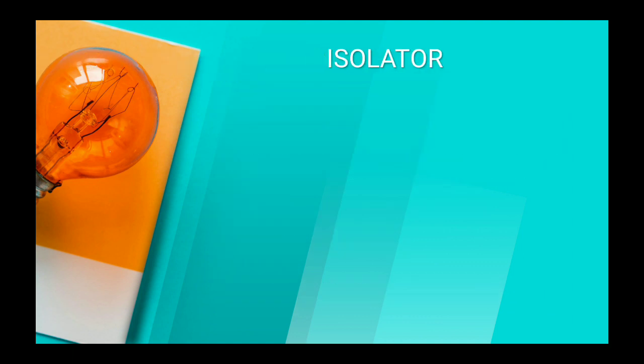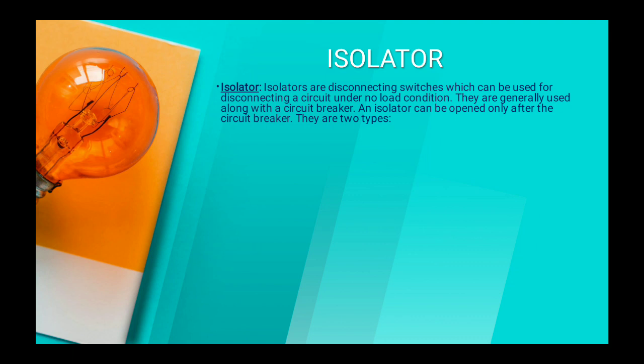Now the next circuit interruption device is the isolator. Isolator means the isolation switch which isolates the healthy electrical part or healthy electrical line from the faulty line. Isolators are disconnecting switches which can be used to disconnect a circuit under no load condition. You can't use it in full load or on-load condition. They are generally used along with the circuit breaker, and the isolator can be opened only after the circuit breaker. The circuit breaker operates in on-load condition and the isolator operates in off-load condition.